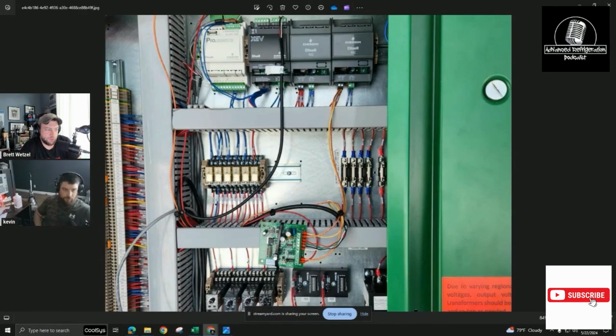Do you have the board where it's configurable? I know they make a universal one with dip switches on it, that's the one you have. So this particular Danfoss valve is 800 steps. Your options are 500, 1596, 2500, and then 6000 for the CDS valve. What was that, Sporlan IB board?